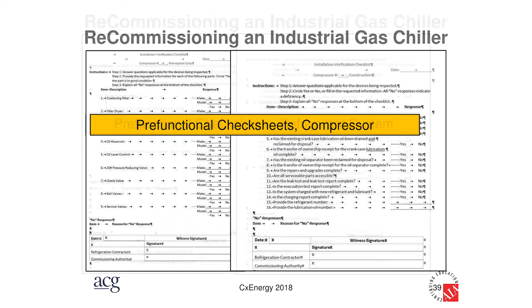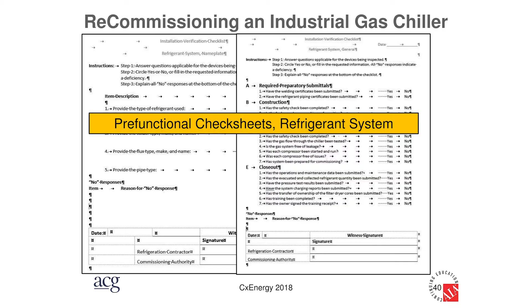Our pre-functional check sheets had, for each compressor, nameplate data, and then also a construction check sheet. Then for the refrigeration system itself, there was nameplate data, the pipe, the refrigerant, the flux, the brazing filler metal, all that sort of thing. All the equipment that we added had its nameplate listed, and then there was the construction side of the refrigerant system also. And it went through, let's see, there was a repair on one of the compressors, there was startup, there was closeout. Closeout included all sorts of, what do they call it, chain of custody for hazardous materials. There was a startup record, there was a record of how much refrigerant went in there, all that sort of thing.